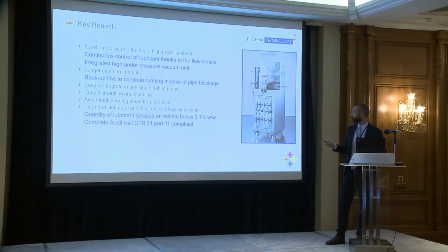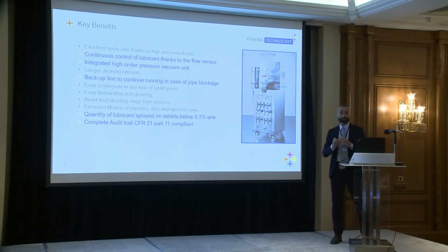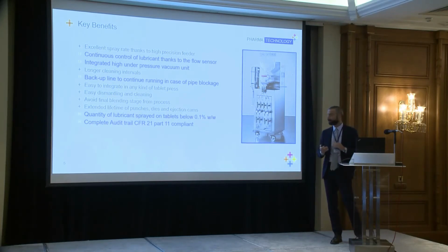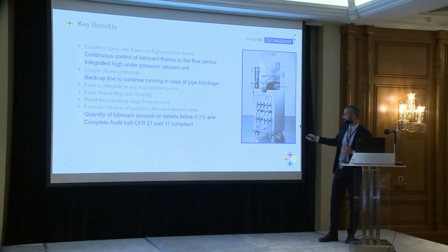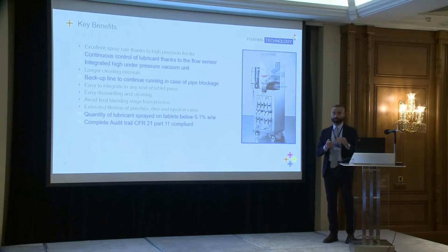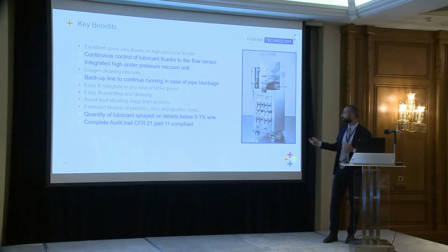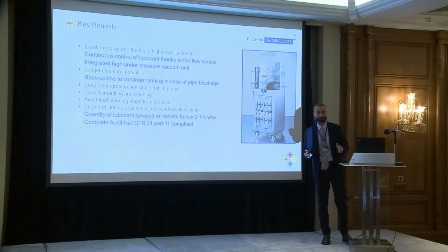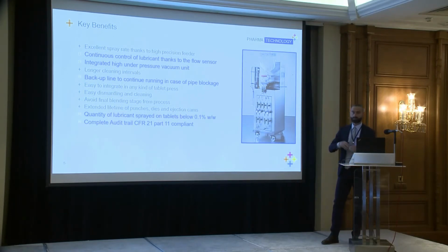The backup line. So now you see here a machine. This was designed for a double side press, but instead of 2 lines, you see 4 lines. Why? The reason is simple. We actually spray only 1 line, but we monitor the pressure on that line from the HMI. When the pressure starts dropping, it means you have a kind of jam inside the line. So automatically, without the need to stop anything in the process, we move from line A to line B, and the operator has the time to remove the line, clean it, and put it back in place. It takes approximately 5 minutes to clean everything, and then it's a loop that doesn't stop.